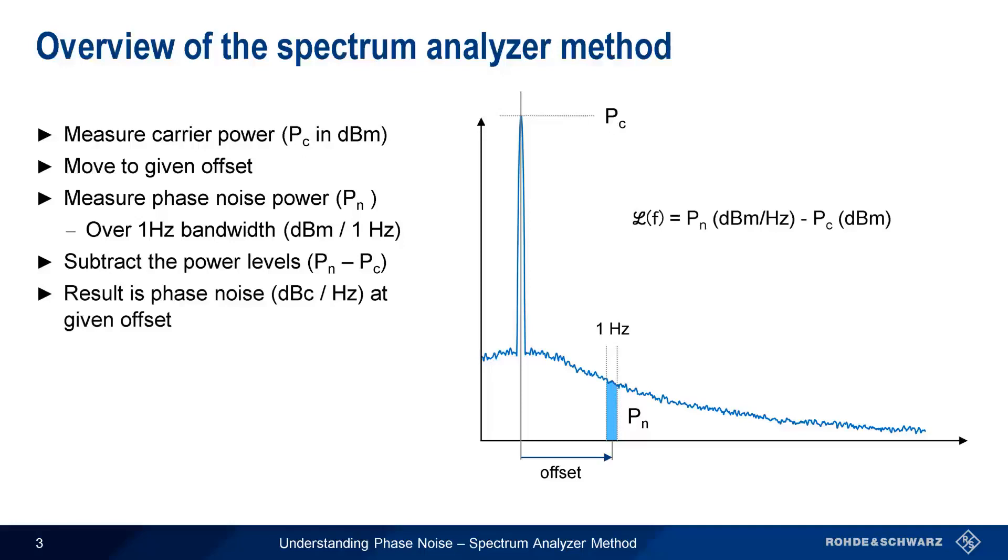Usually these measurements are repeated for various offset values, and the results can be displayed either graphically or as individual spot noise values in a table. When making phase noise measurements with a spectrum analyzer, there are two additional steps that we need to take: normalization and shape correction.